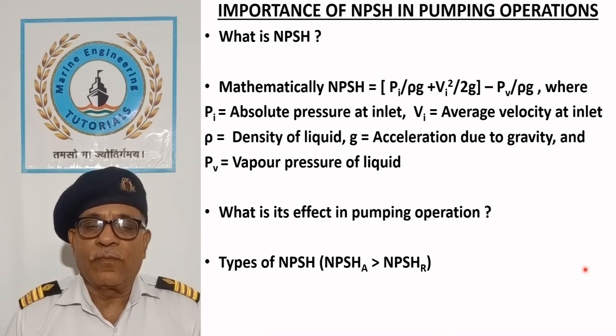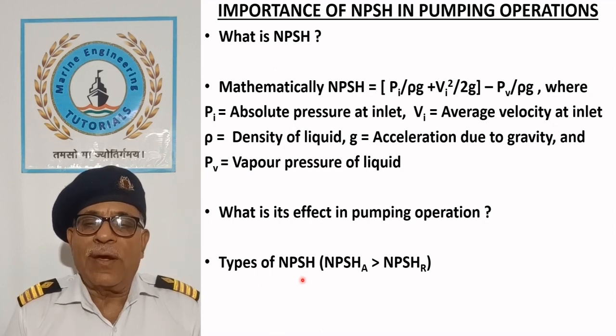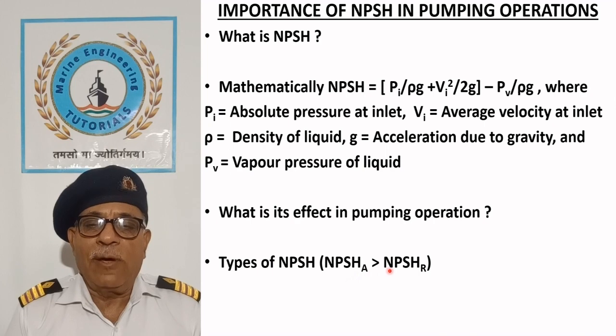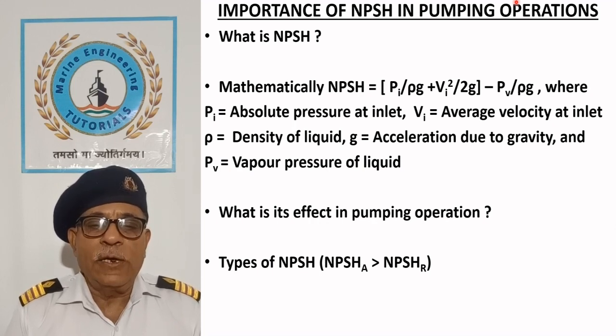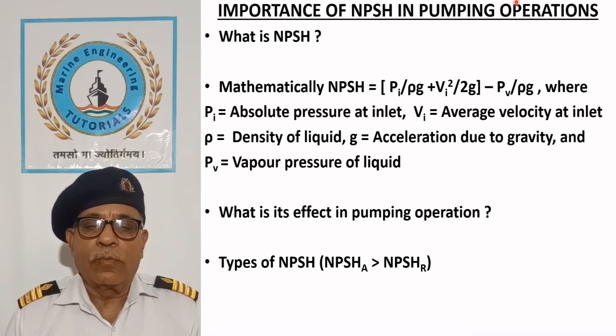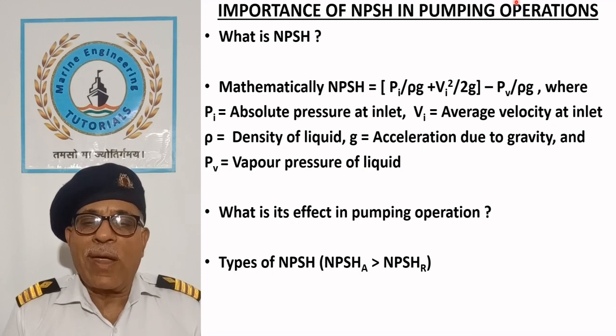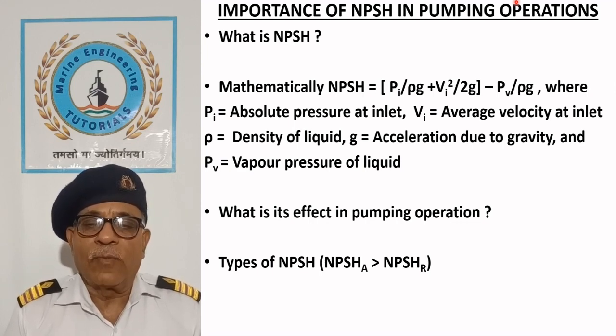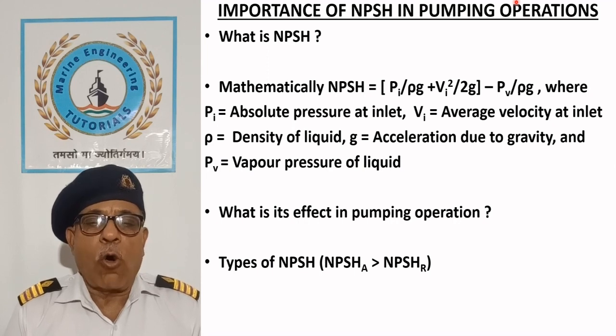Types of NPSH: Net Positive Suction Head can be divided into two types — NPSHA, which means Net Positive Suction Head Available, and NPSHR, which means Net Positive Suction Head Required. For a pump to operate satisfactorily, NPSHA should always be in excess of NPSHR, otherwise the pump will cavitate. NPSHR depends on the pump design, whereas NPSHA depends on the pump installation.